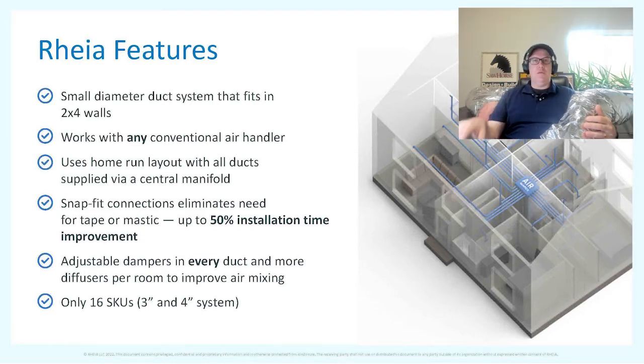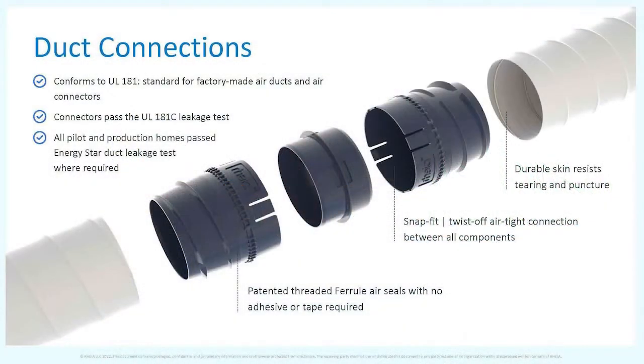With the Rheia system, each duct runs all the way from the manifold in the mechanical room to the room where you need it, with no chance of air loss between those two points. There's one standard duct size — three inch, or four inch if needed. All couplings are the same and there are only 16 SKUs, meaning you can design the system, order the parts on a pallet or two, and it all snaps together without needing deep HVAC duct design knowledge.